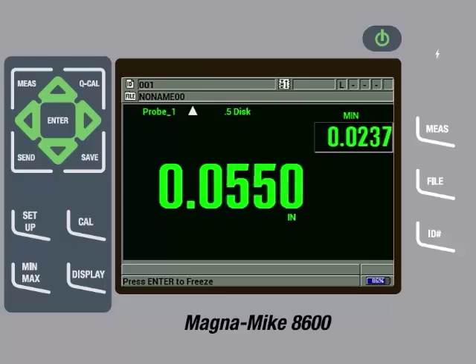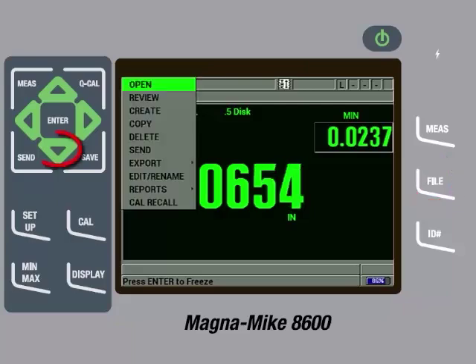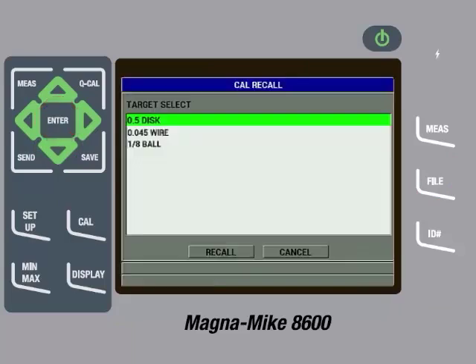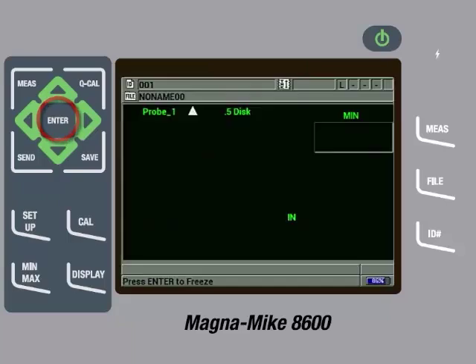Now, if another target is used, and the customer wants to recall the setup for the disc target we just used, they can press the File key and then keep pressing the down arrow until Cal Recall is highlighted. Then they can press Enter. Here we see a list of calibrated targets. The user can highlight the 0.5 disk target and then press Enter, and then press Enter again on recall.